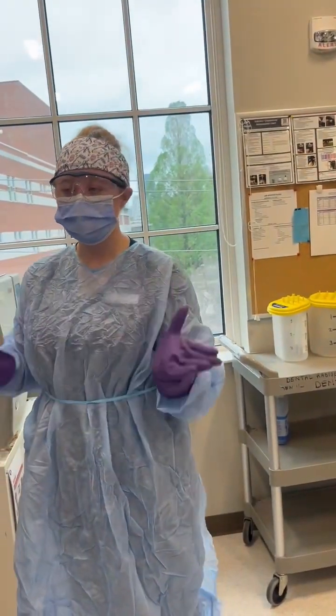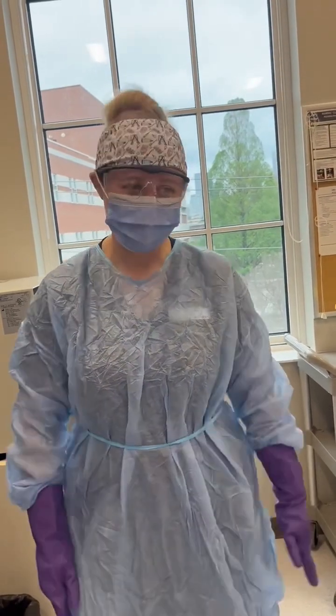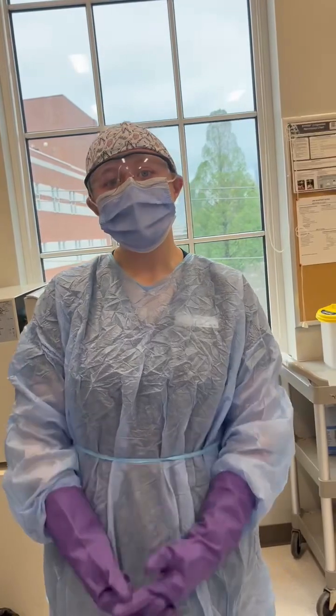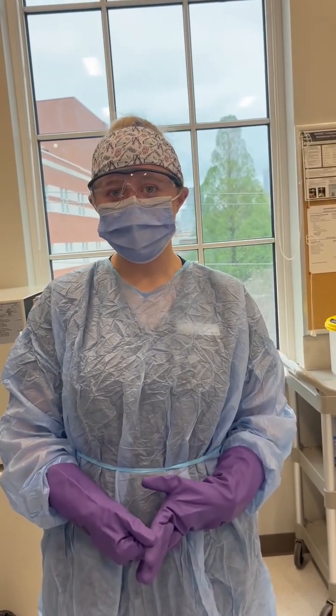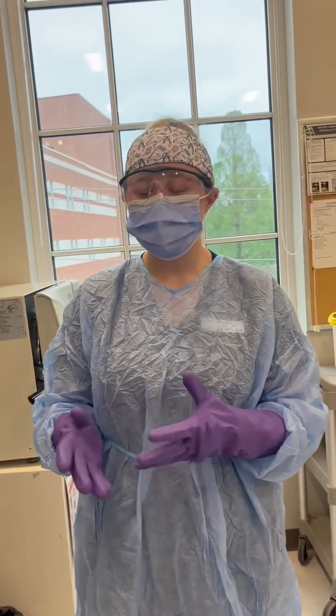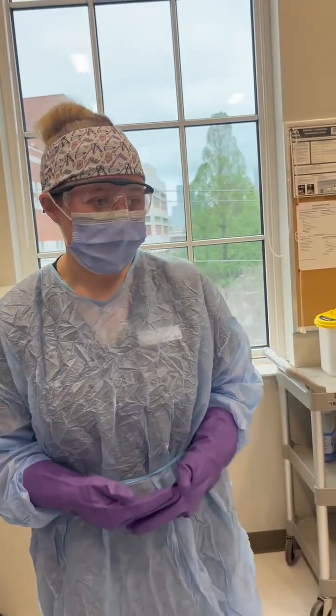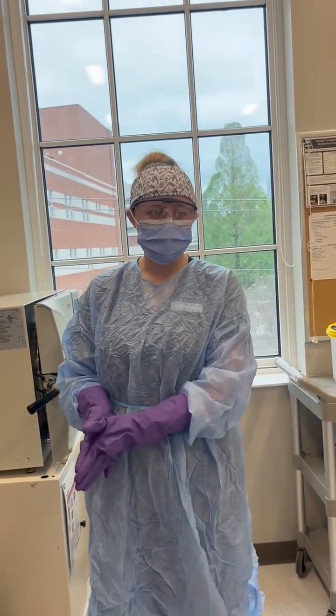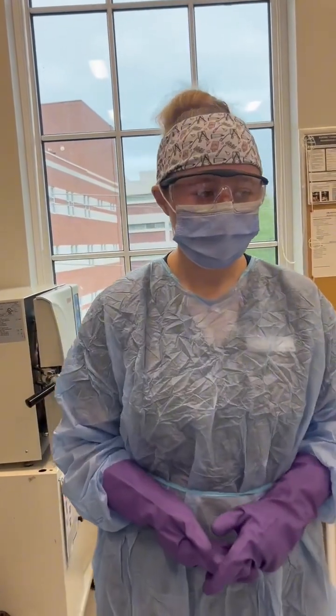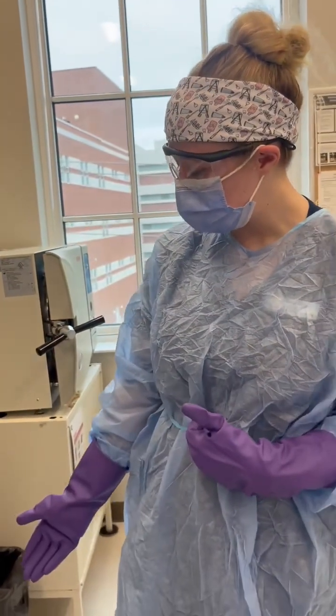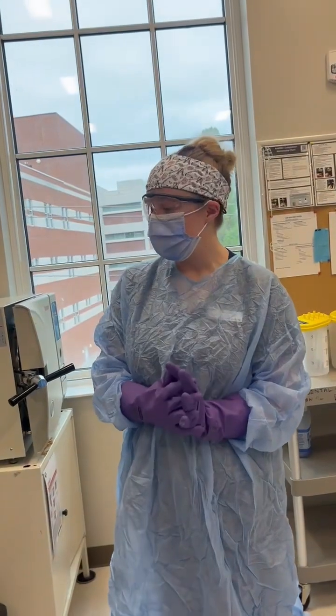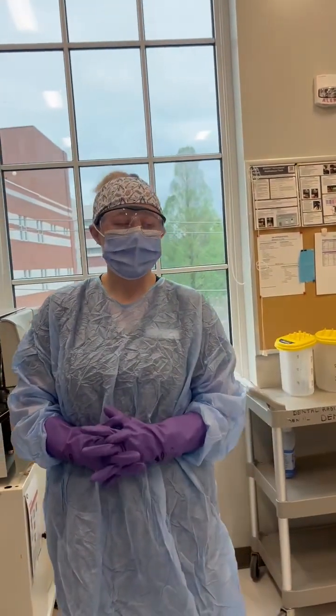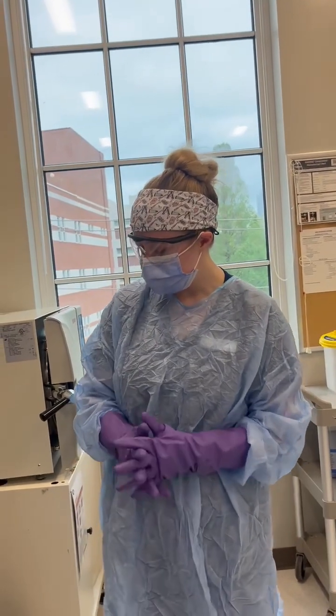Much like the other autoclave system in the dental facility, you need to check the water to make sure it is at a good level, and if it's not, you need to fill it with distilled water, and distilled water only. When loading it, you need to make sure that the instruments are not too tightly packed in there in order to let steam effectively circulate. You must use the appropriate sterilization cycle based on the type of instrument you are using. After the sterilization has been complete, you would just drain it like you would any of the other sterilizers. And there is a button on the bottom to turn it off.